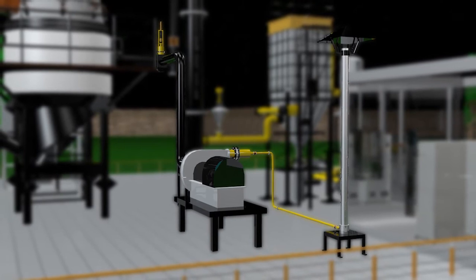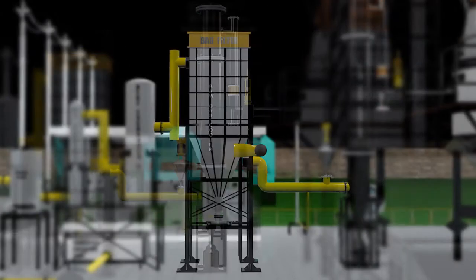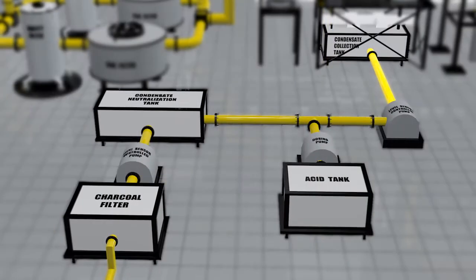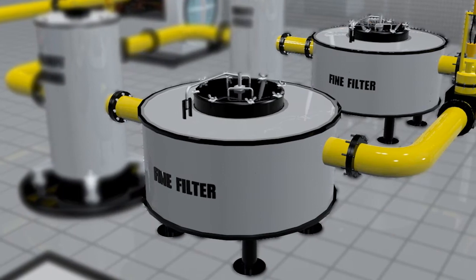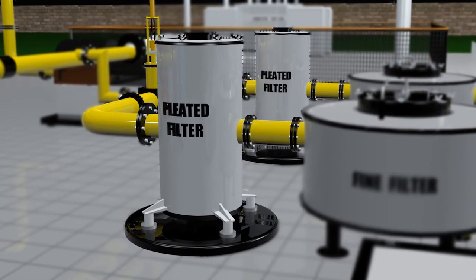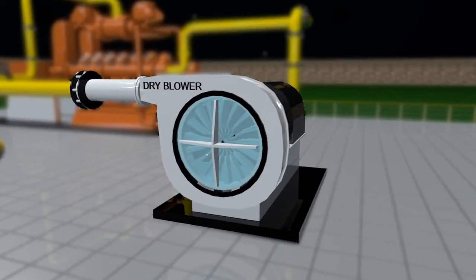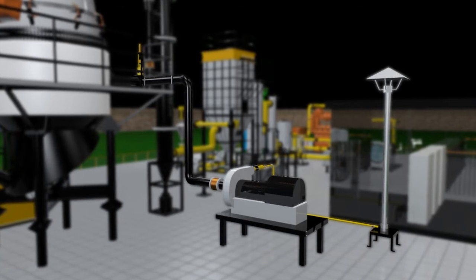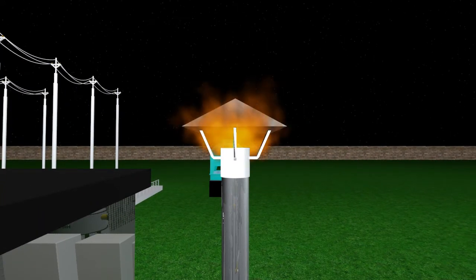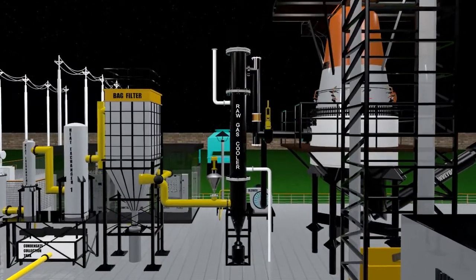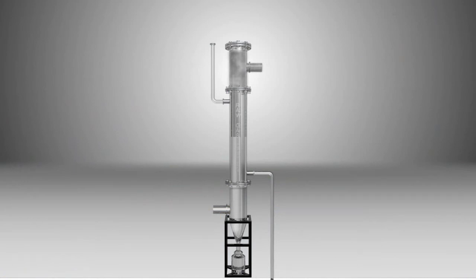The dry filtering system consists of a startup subsystem, a gas temperature control subsystem, an automated ultra-gas purification subsystem, a condensate removal subsystem, a condensate treatment system, fine filters, pleated filter, and a dry blower. The gasifier is started using the startup subsystem. The gas passes through this circuit till it reaches a temperature of about 450 degrees centigrade. Once that temperature is achieved, the gas is allowed to pass through the gas temperature control subsystem where the gas is cooled to about 250 degrees centigrade. Here ambient air is used for cooling the gas. This allows some heat recovery.